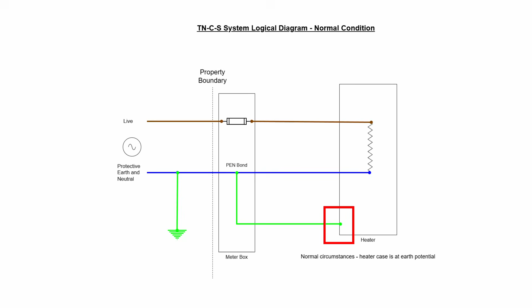Let's look back at the logical wiring diagram we showed last time. This is a simple representation of an electrical installation showing an incoming electrical supply feeding a resistive heater. We see in the diagram that there's an electrical circuit from live through our appliance back along the neutral wire as normal. In this TNCS system, the neutral inside the property connects with the CPC at the entry to the property, often in the meter box. That's what's unusual about the wiring of a TNCS system. As our heater has a metal case, we've connected that case to the CPC. We consider that safe because the CPC should be at the same voltage as the ground on which we stand, the literal planet Earth.